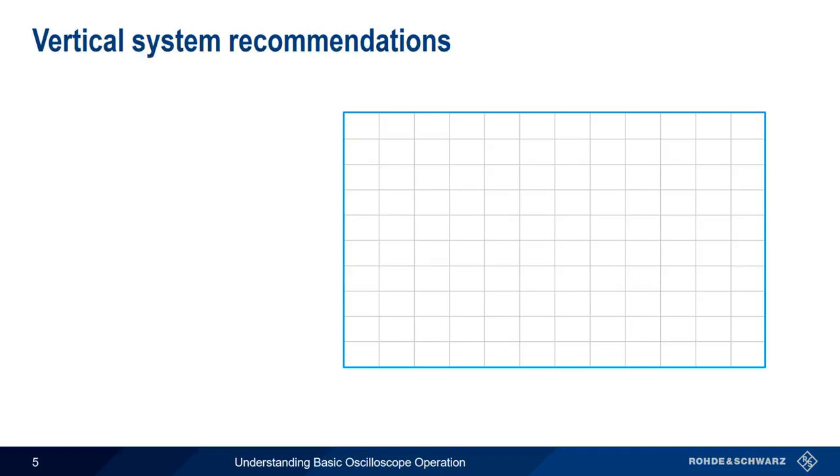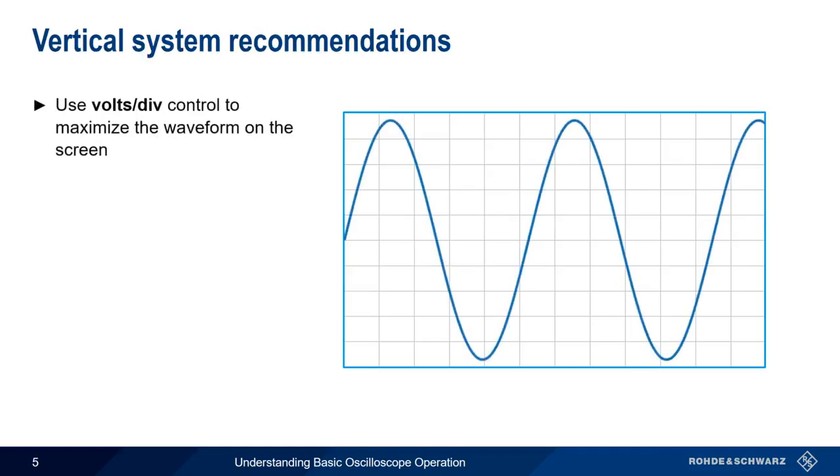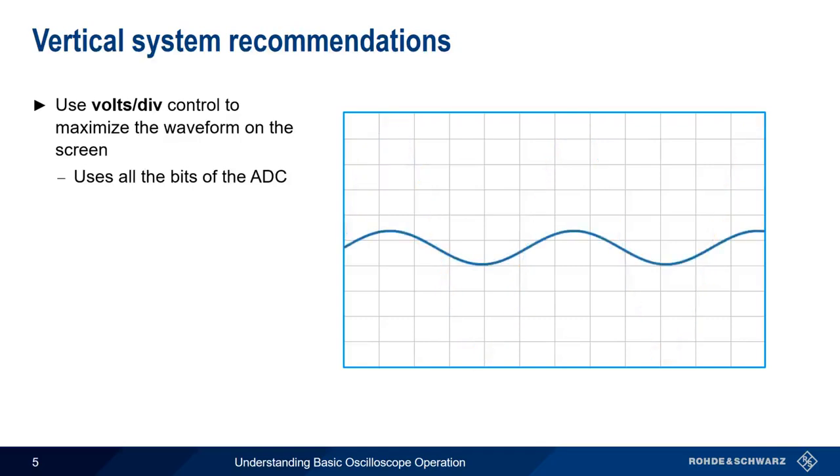The most important thing to keep in mind when configuring the vertical system is to use volts per division to maximize the waveform on the screen. In other words, to have the positive and negative peaks as close to the top and bottom as possible without clipping the waveform. By doing this, we ensure that we're using all of the bits of the scope's analog to digital converter. If we don't use the entire vertical scale, then we're not taking full advantage of the scope's ADC. It's also easier to see small details or features in the waveform when we maximize our use of the vertical scale.